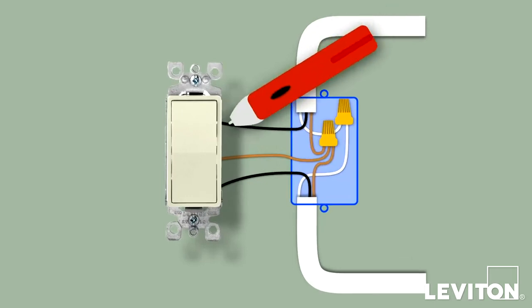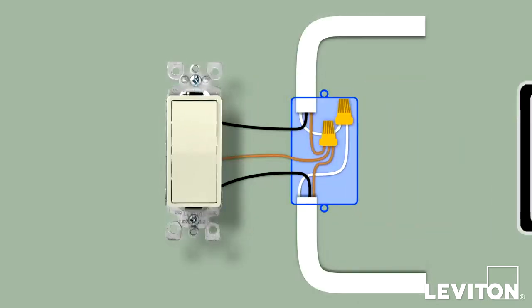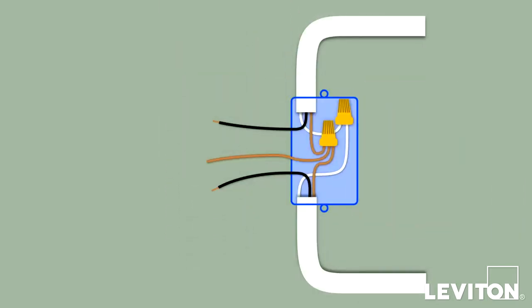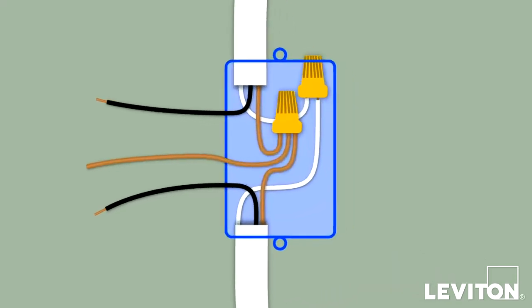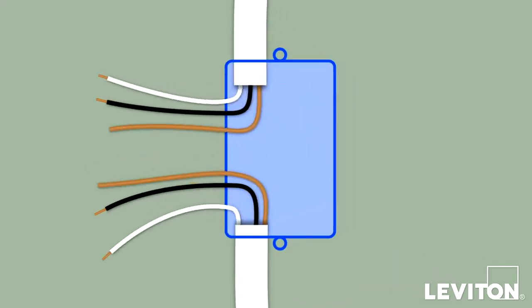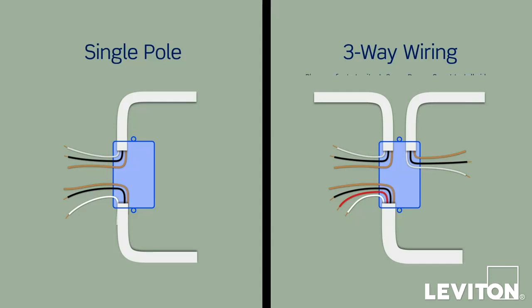Use the voltage tester to ensure that there is no power present in the box. While the old devices are still connected, take pictures of the current wiring. Carefully disconnect all the wiring from the old device and remove it. Straighten and separate each wire so that you can clearly see them. Make sure that none of the exposed metal ends of the wires are touching each other. Now, you'll need to identify whether the wiring application is a single pole or a three-way application. If wiring in the wall box does not resemble either of these configurations, consult an electrician.